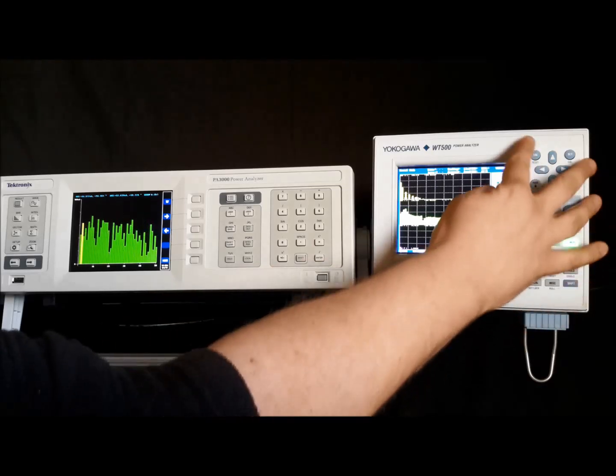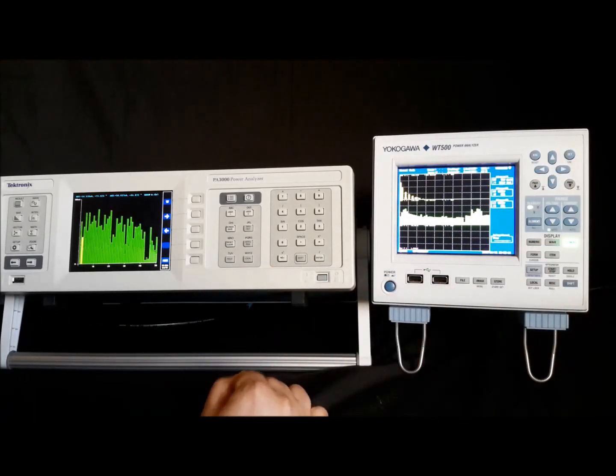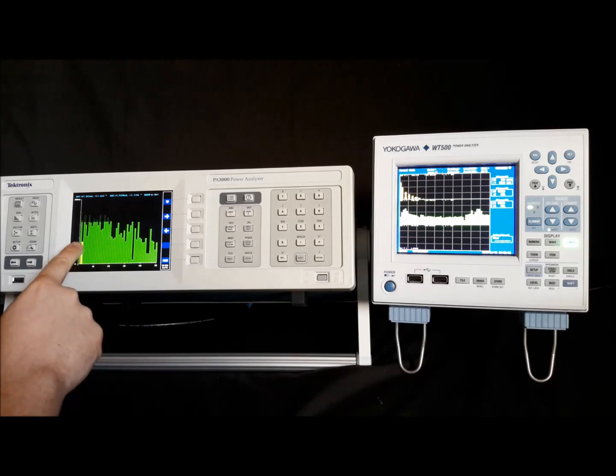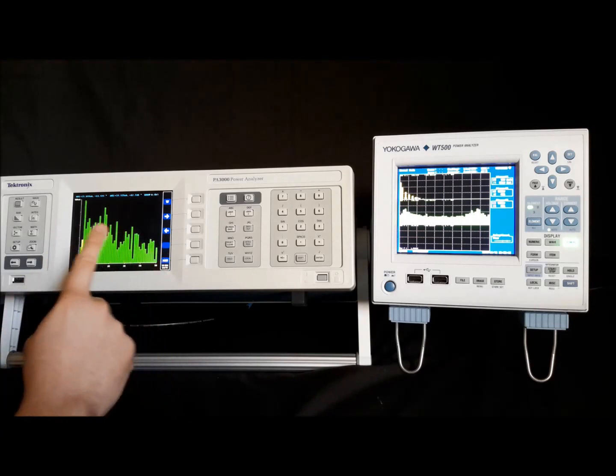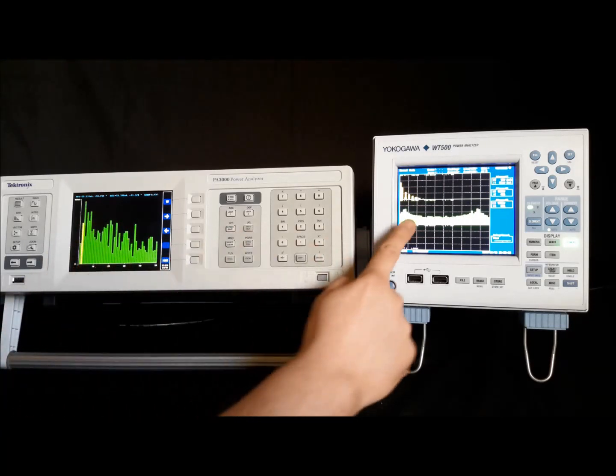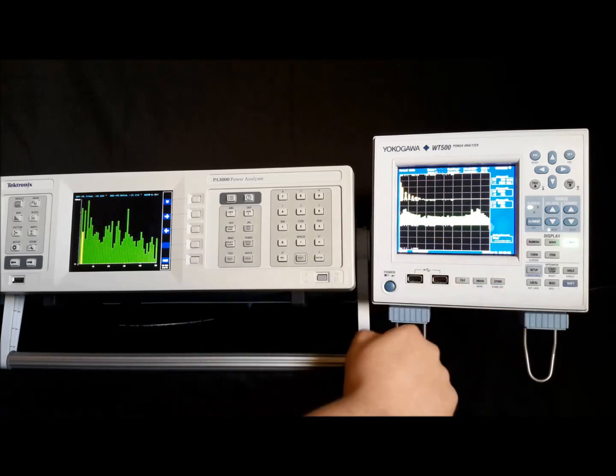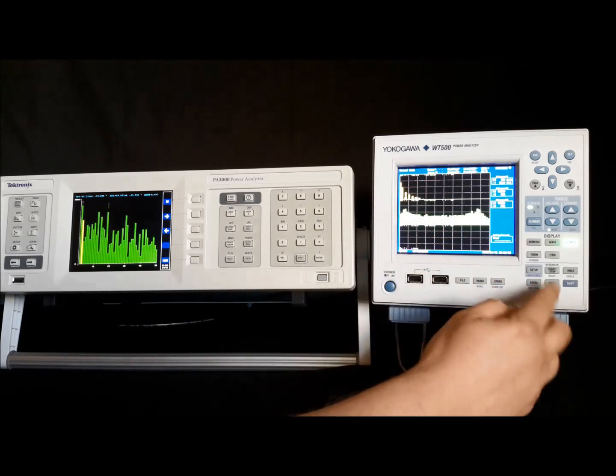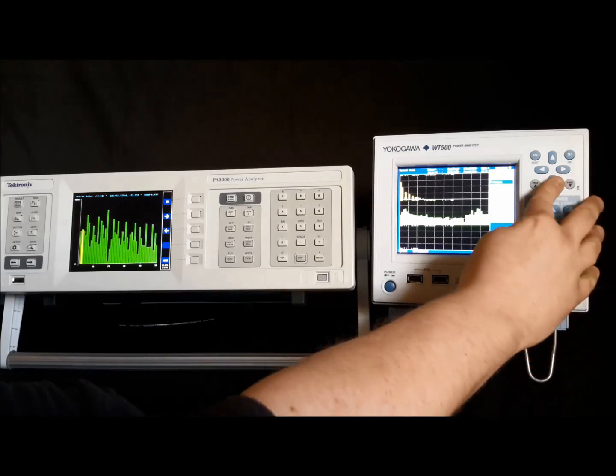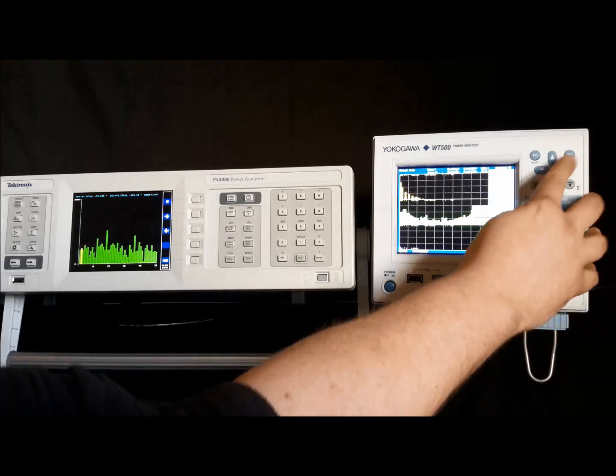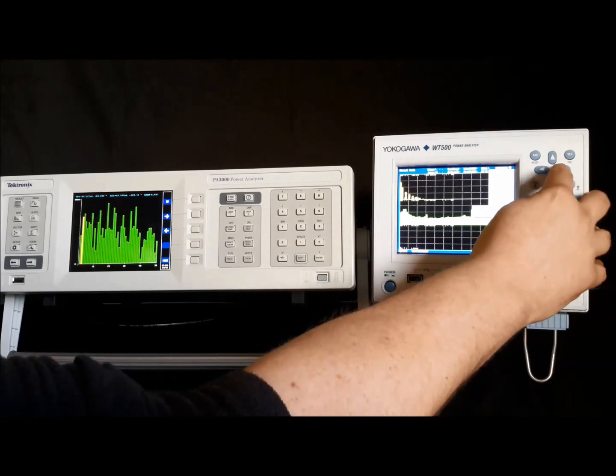One concern, looking at this, is there's quite sporadic readings on the current harmonics on the Tektronix. The WT500 appears to be more stable. Let's increase the update rate and see if that changes anything - 10 times a second.